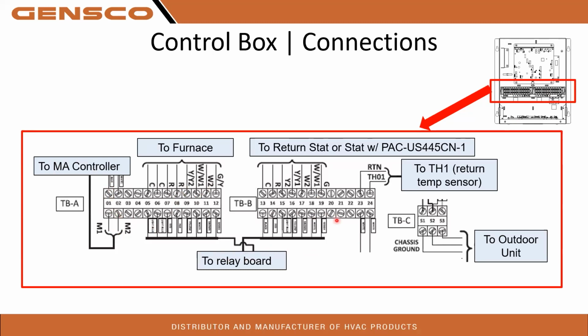Your relay board is down here on the bottom. Your return temperature thermistor. So this is the one where the guys get mixed up that I was talking about earlier. That thermistor with the bare copper end on it is the return temperature thermistor. It is going to wire into here to TH01 and RTN. If you're using a non-adjustable thermostat, which is on the next slide I'll show you, it's going to wire into your thermostat controls over here. And if you're using a 24-volt thermostat, you do not need that non-adjustable stat. But again, furnace is going to wire up on the left on the TBA. Your thermostat and your temp sensors are going to wire up on the right on TBB. And then your S1, S2, S3 is going to wire up the TBC.